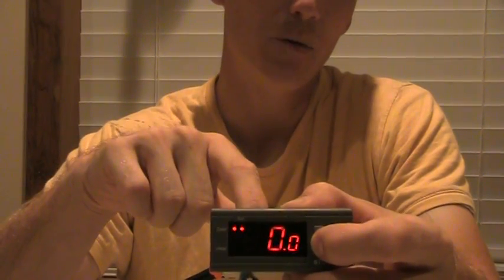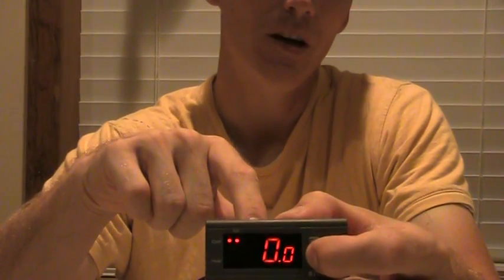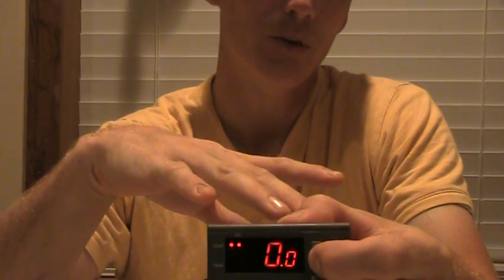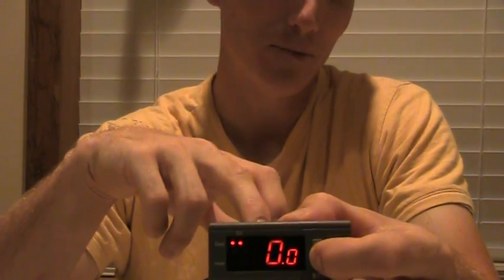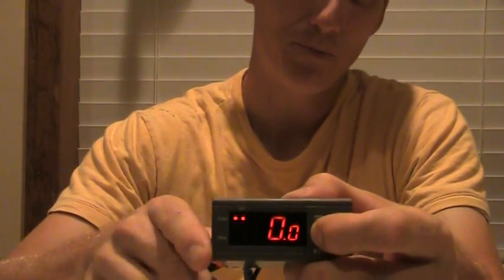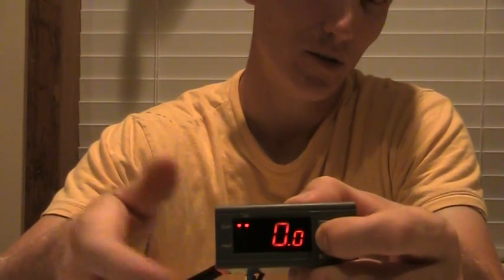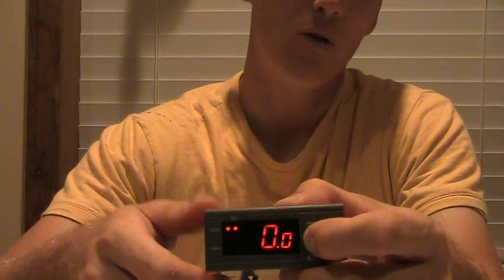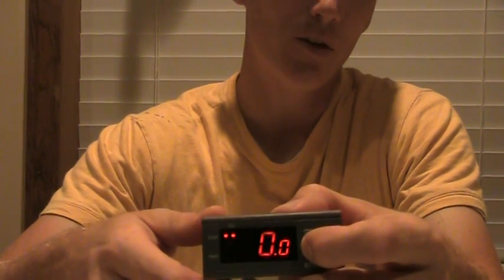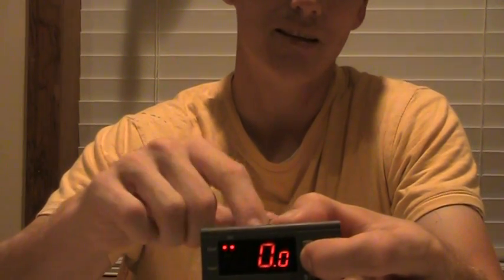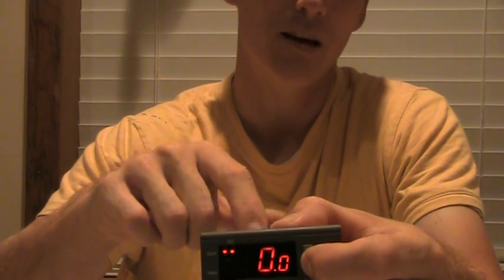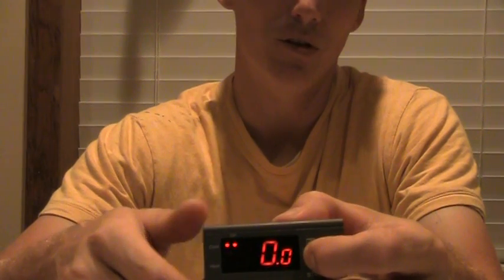What F4 is, is a calibration setting, allowing you to raise it up or down if you need to calibrate your thermostat. Over the years, sometimes they'll get a degree or two off. You'll have to test them using a glass of water and ice, set it to 32 degrees, and if it's not exactly 32 degrees, then you'll move it up or down to calibrate it.